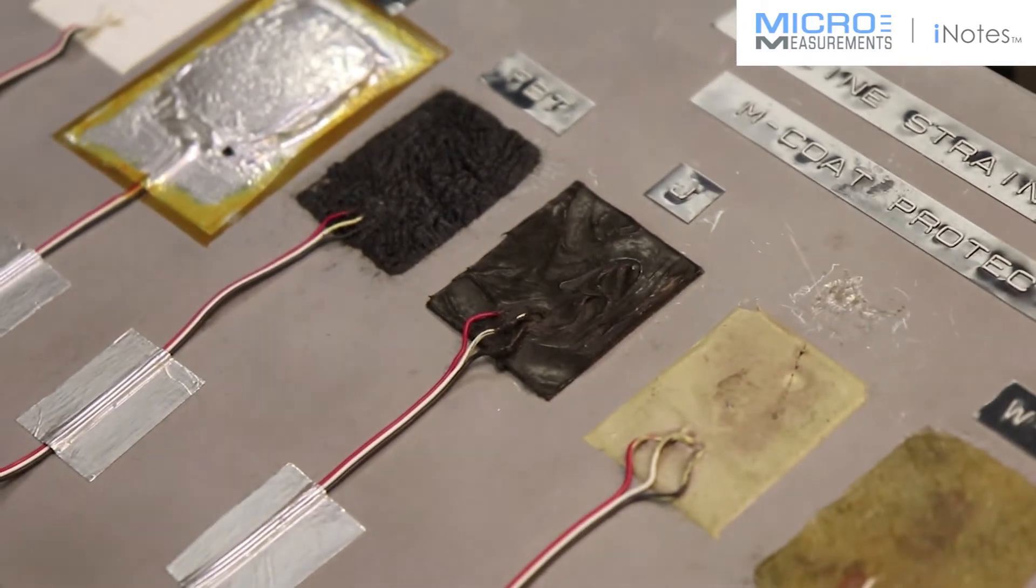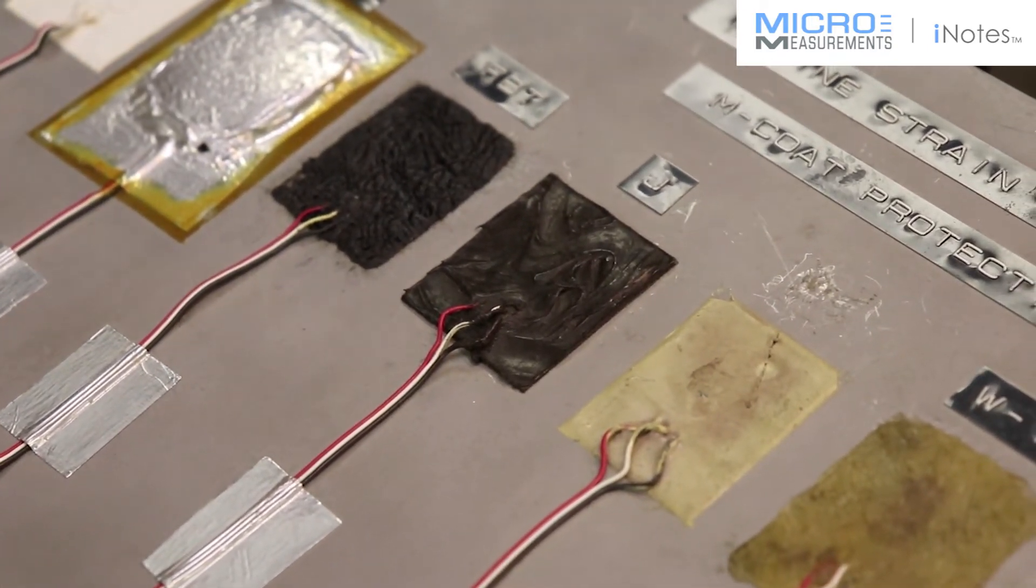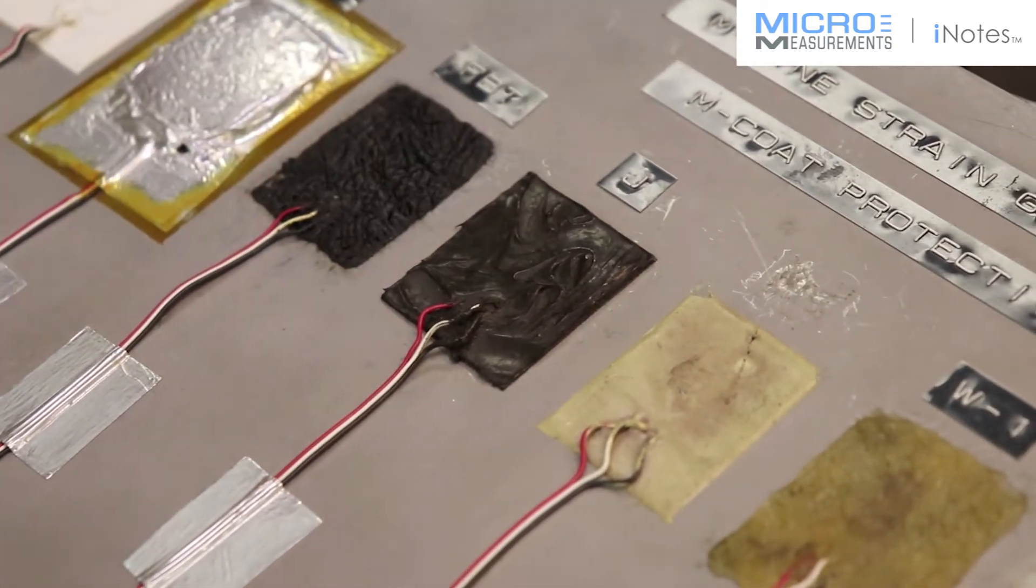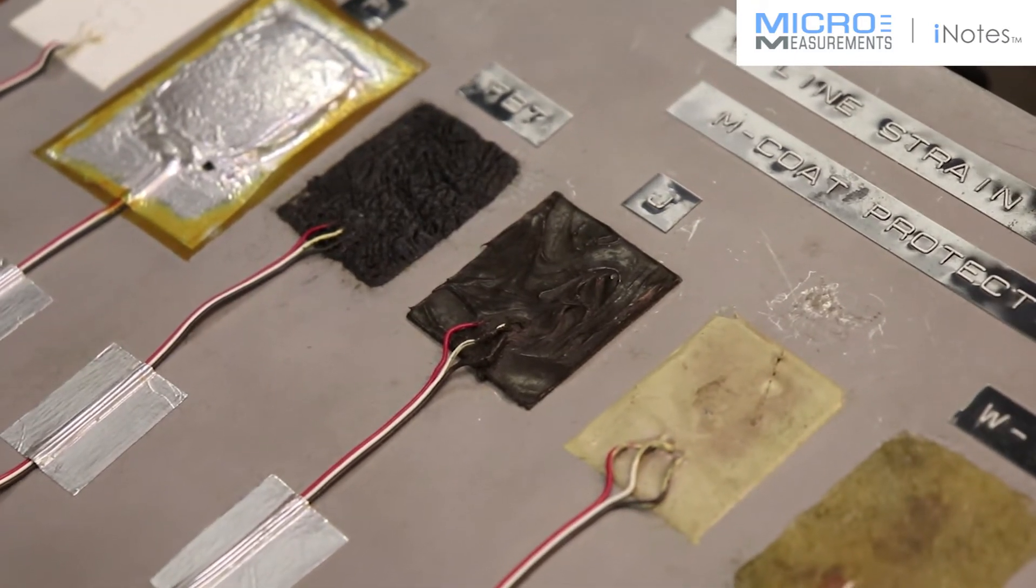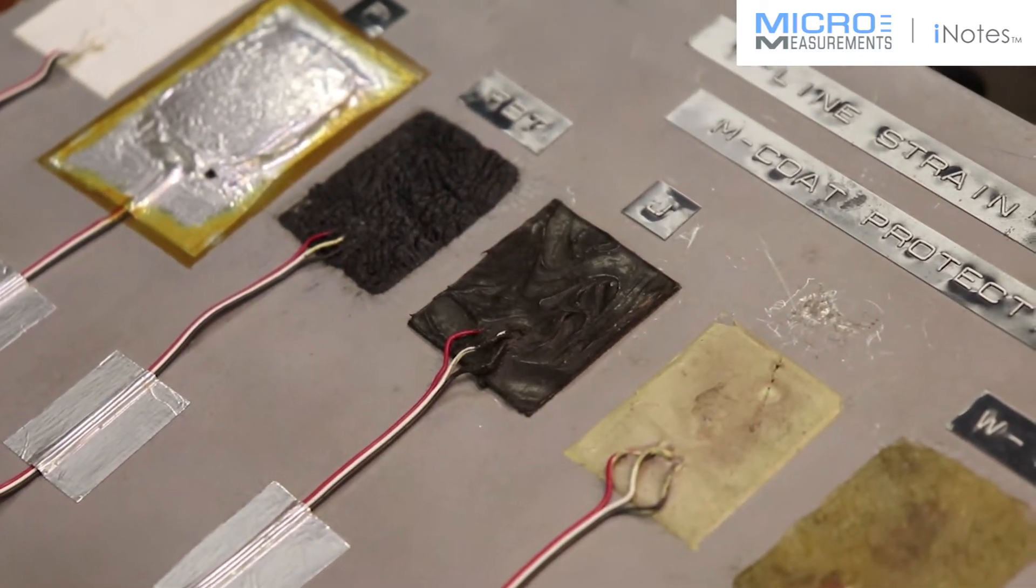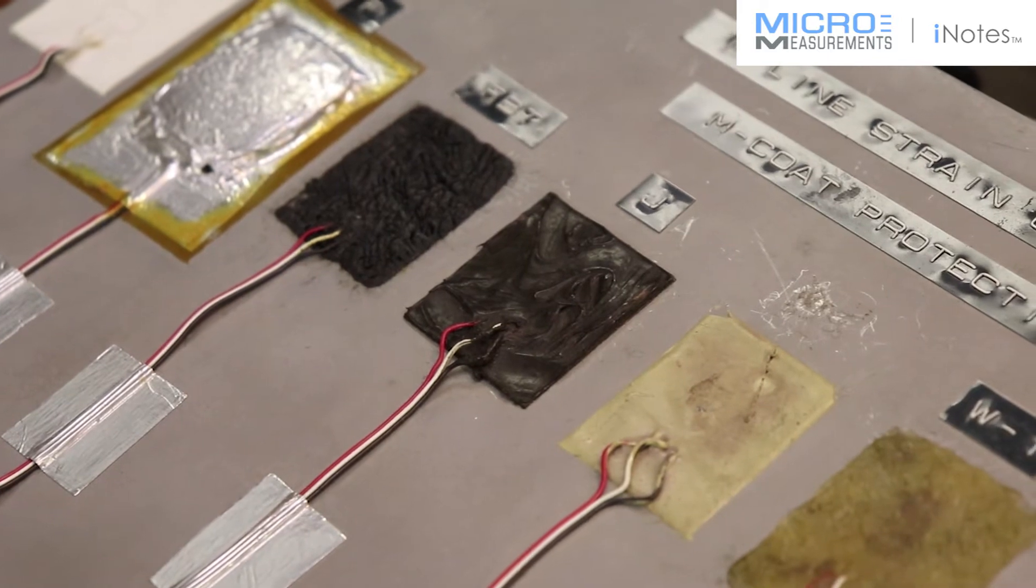It's still flexible but it's an excellent vapor barrier. The one drawback is its resistance to ground characteristics are poor for the first 30 days. So you might want to be sure and understand the instability that might occur then.